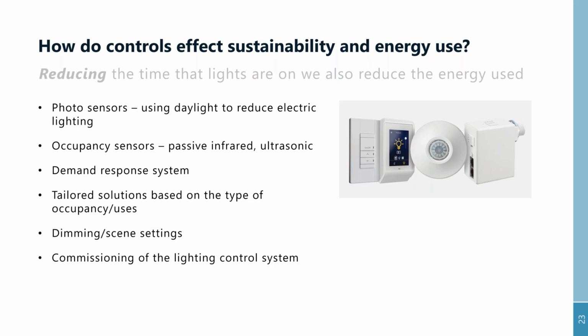Photosensors detect the daylight to reduce electric lighting. Occupancy sensors detect when people are in the space, turning the lights on when someone enters and automatically turning them off after a set time. There are a few types: passive infrared, ultrasonic, and dual tech.